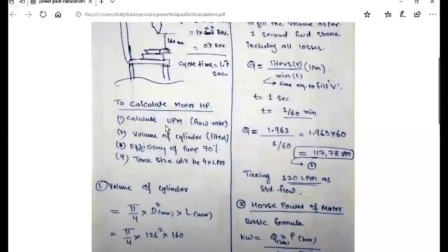First we need to calculate the LPM, liters per minute, how many liters per minute we have to input or the flow rate of the oil. Then volume of the cylinder, efficiency of the pump we take approximately 70%, and the tank size should be four times the LPM or liters per minute, that is the rule.